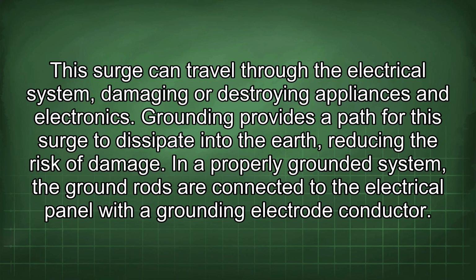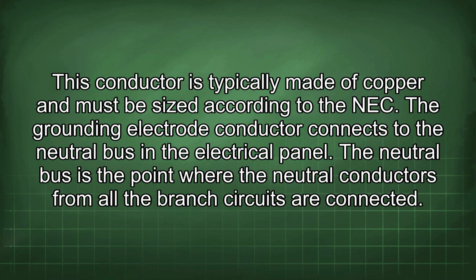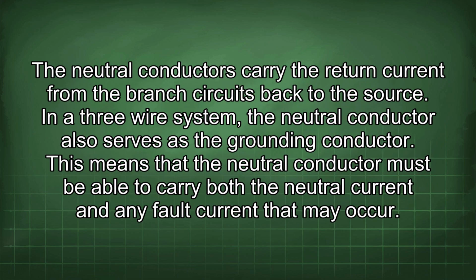In a properly grounded system, the ground rods are connected to the electrical panel with a grounding electrode conductor. This conductor is typically made of copper and must be sized according to the NEC. The grounding electrode conductor connects to the neutral bus in the electrical panel. The neutral bus is the point where the neutral conductors from all the branch circuits are connected. The neutral conductors carry the return current from the branch circuits back to the source.